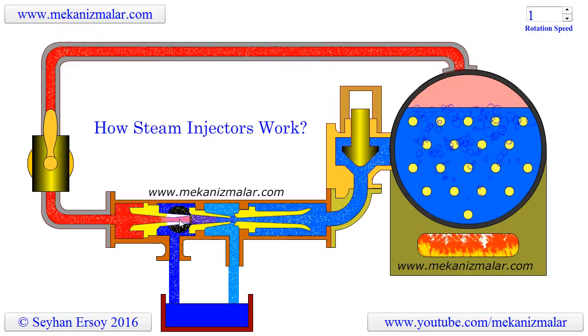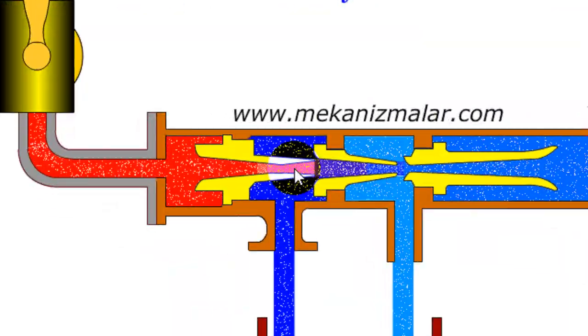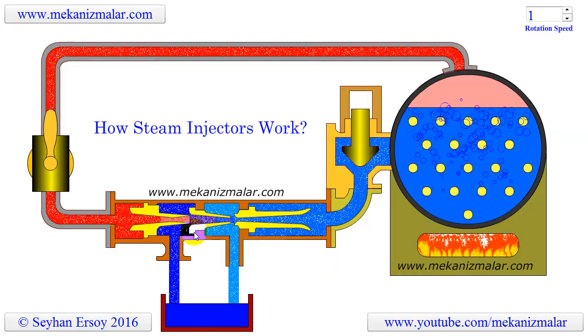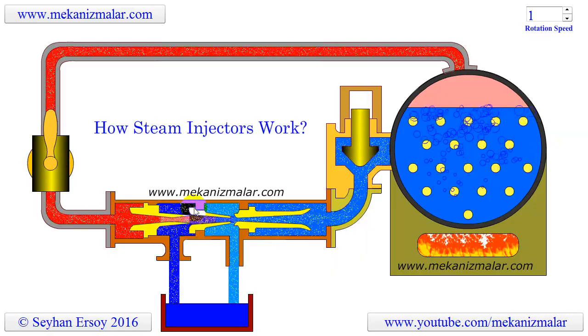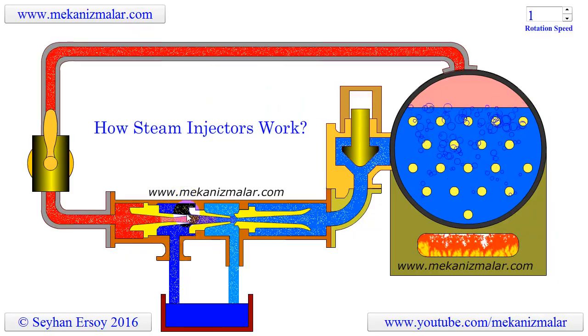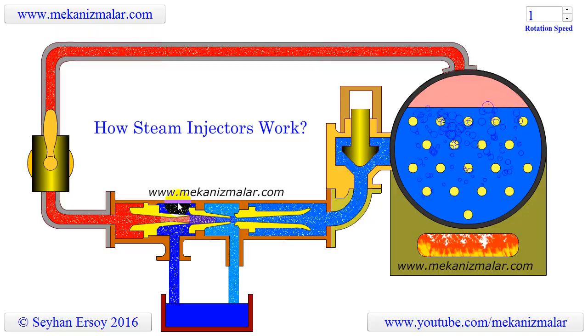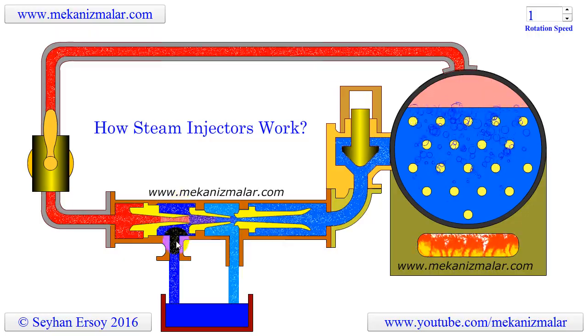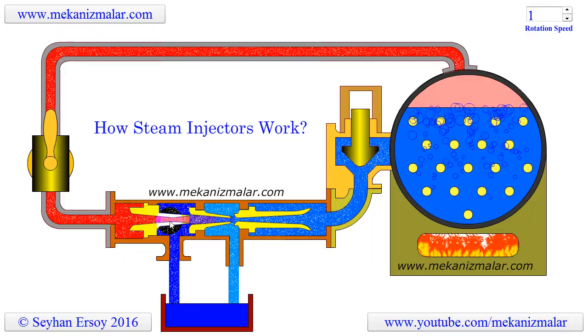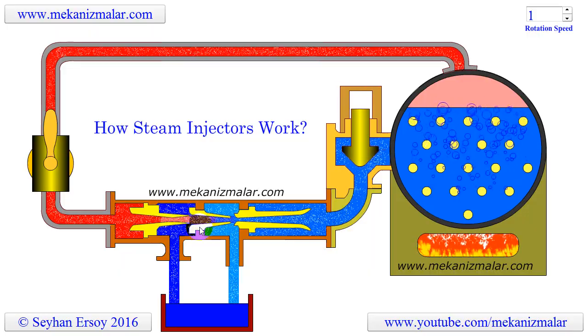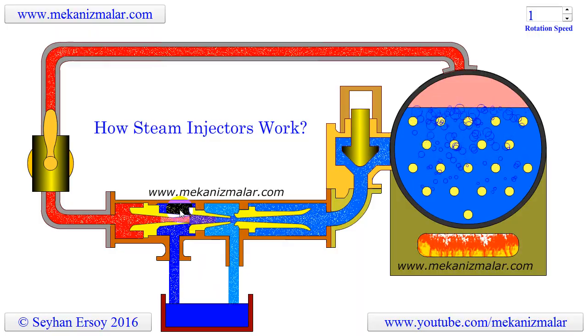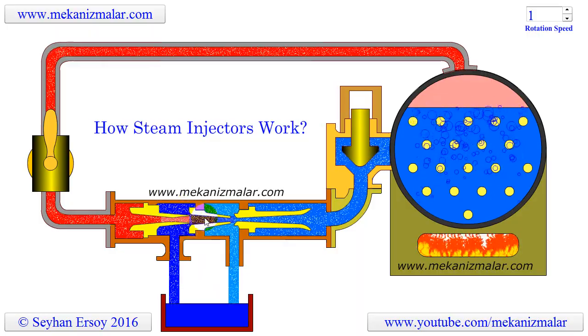The low pressure created at the exit of the steam cone causes the water in the reservoir to be sucked into the vacuum chamber. The steam leaving the steam cone with high velocity enters the combining cone, so called because the steam is also sucking large amounts of water from the reservoir.